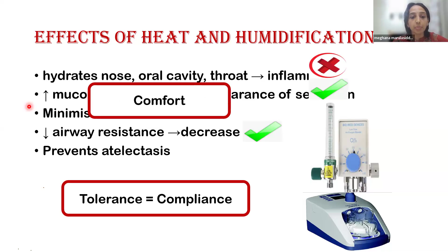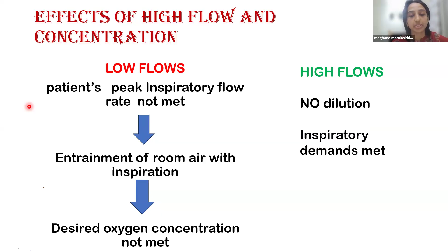Now, let us see what happens when we provide gas at low flows and high flows. When we provide low flows, that is our conventional methods, the patient's peak inspiratory flow rate is mostly not met. And due to that, there is some entrainment of room air with inspiration. This causes dilution of the air or oxygen that the patient is breathing, and the desired oxygen concentration is not met. Whereas when we give high flows, there is no dilution and the inspiratory demands of the patient are met.